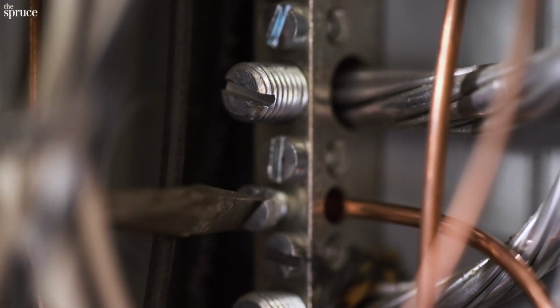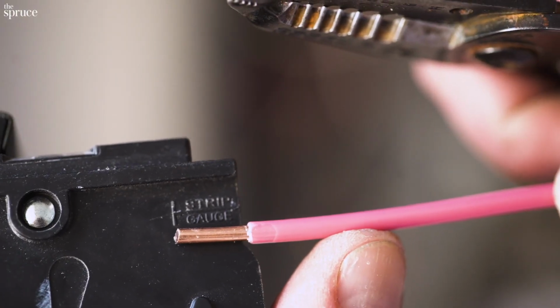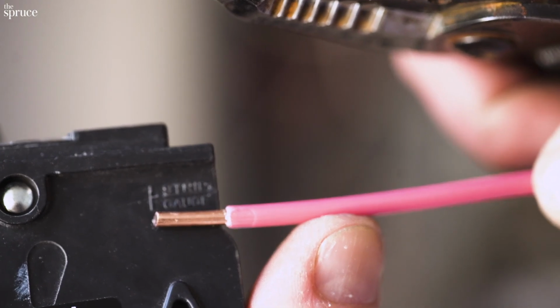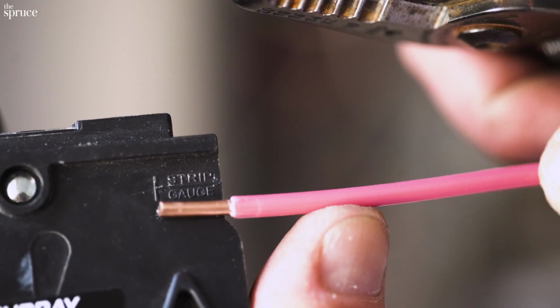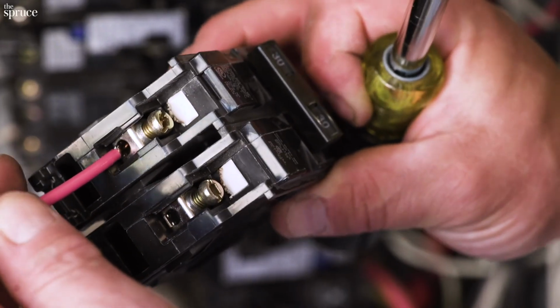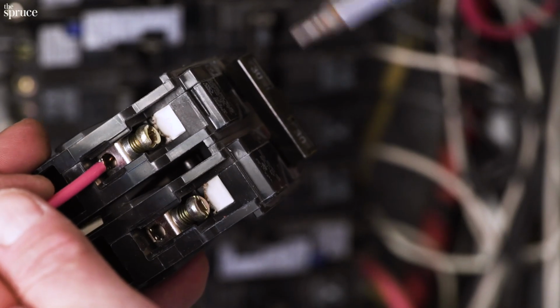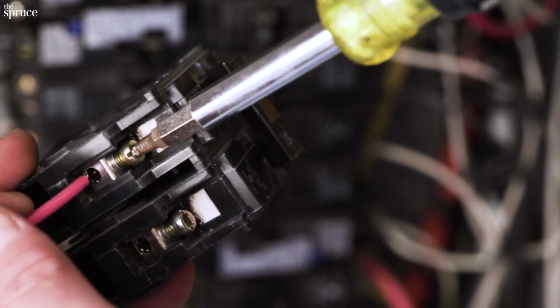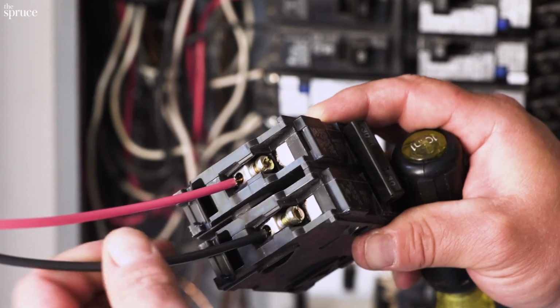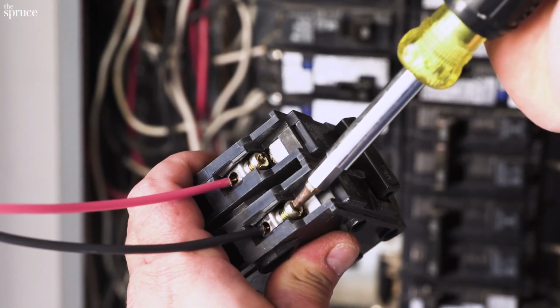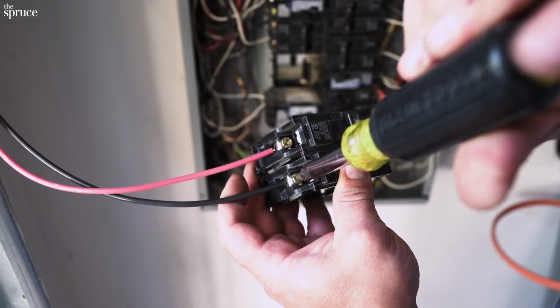Okay, now for the hot wires. There's a little strip gauge on my circuit breaker that tells us how much of the wire insulation to remove. This looks about right. So we'll slip in the red hot wire into one terminal and the black into the other and tighten each screw. You want to get these really tight so there's no chance of these coming loose. Once it's wired up, it's time to install the breaker.